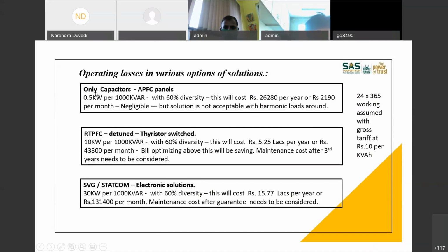The first case I have considered here is, let's say you have used only capacitors. Capacitors typically have only 0.5 kilowatt loss per 1000 kVAr with 60% diversity. If you calculate this, it comes to around 26,280 rupees per year and 2,190 rupees per month, which is negligible. For a 1000 kVAr capacitor panel, the plant's electricity bill per month will probably be at least 15 to 20 lakhs. So they can easily absorb this 2,190 rupees loss in the capacitor panel, and they don't have to even think about it before installing, because the power factor correction benefits will be much more compared to this.